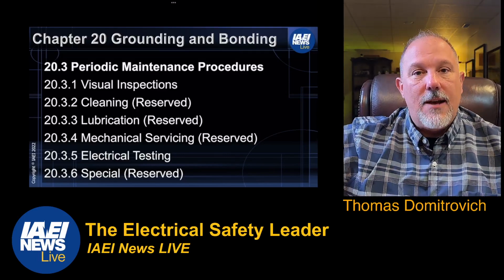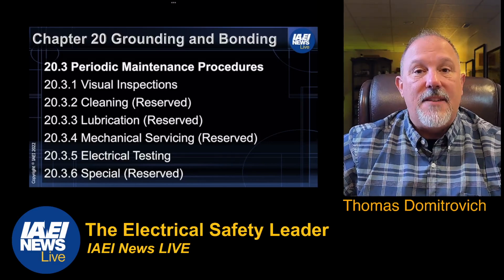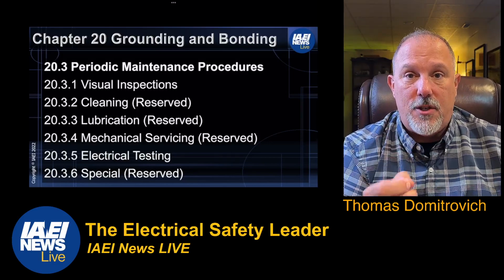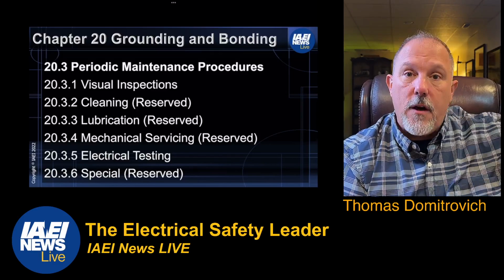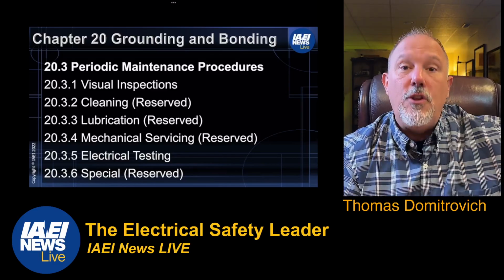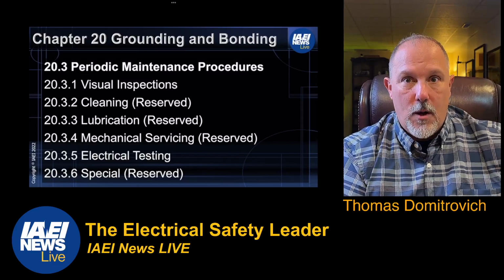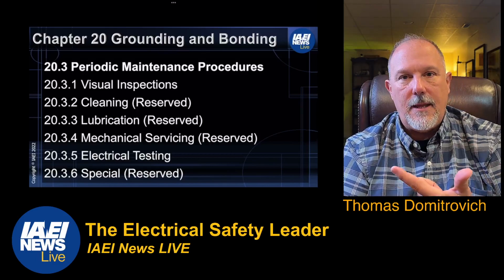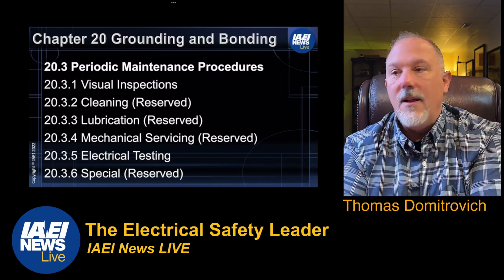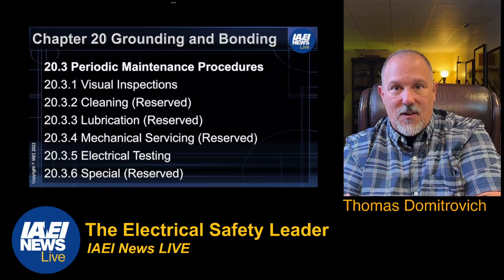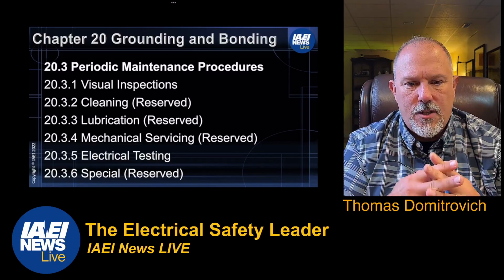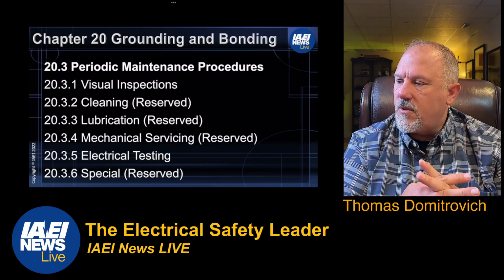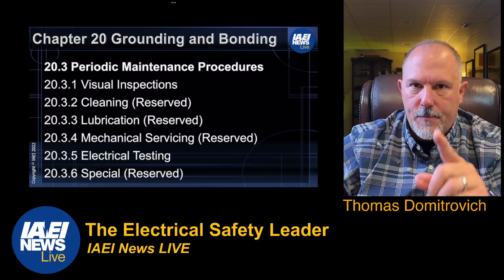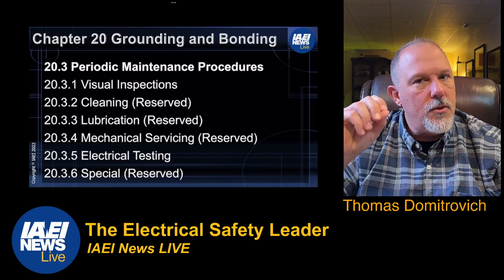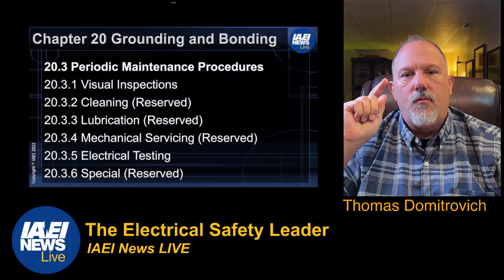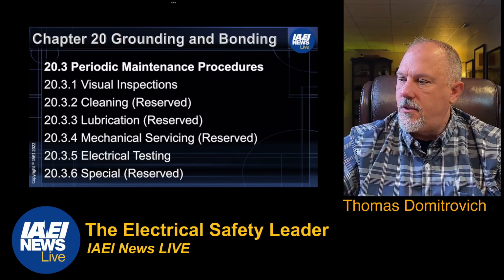So NFPA 70B is not going to tell you how to make that termination. NFPA 70B is going to tell you that you better have followed the National Electrical Code and manufacturer's instructions when you installed the equipment to ground and bond it. But 70B is not going to tell you that - 70B is going to tell you how to inspect after the fact. Do you see the relationship here? So we're going to look at visual inspections and we're going to look at electrical testing. But be mindful that initial installation should follow the right requirements and manufacturer's instructions.